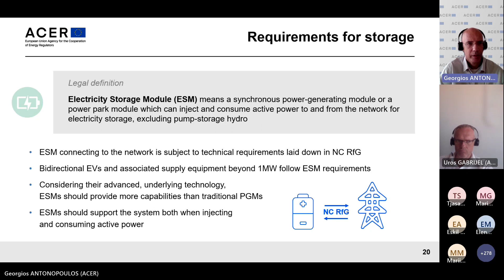And these are some requirements for storage. We have the general requirements for all PGMs, power generating modules, and we have requirements for all synchronous power generating modules or requirements for all power park modules. And then we have additional requirements for electricity storage modules. So we have limited frequency sensitive mode for over frequency and under frequency response, adjusting injection or consumption, modulation of active power input or output following the instruction, and electricity storage module provides capabilities based on their maximum energy storage. And of course, the possibility to switch between injecting and consuming is also required.